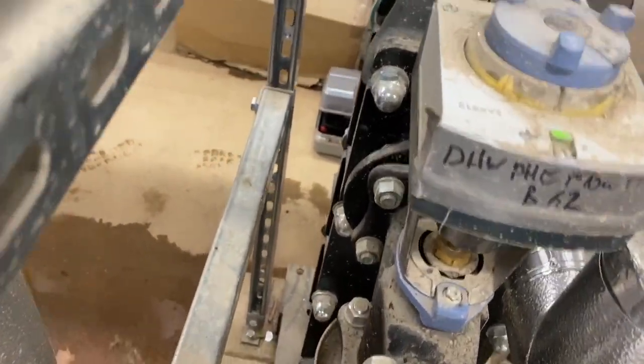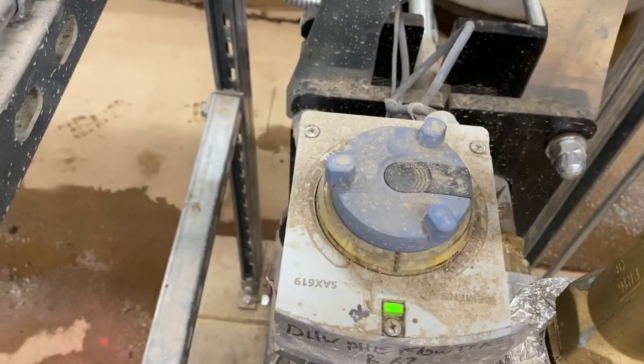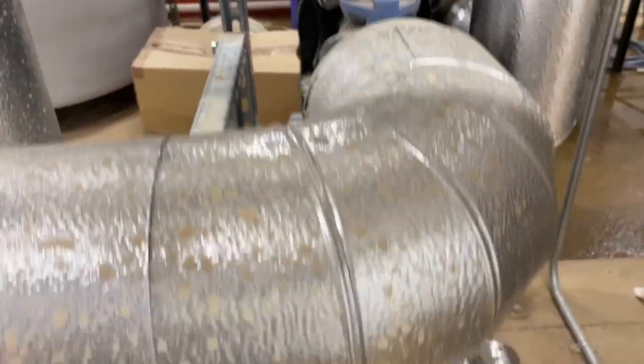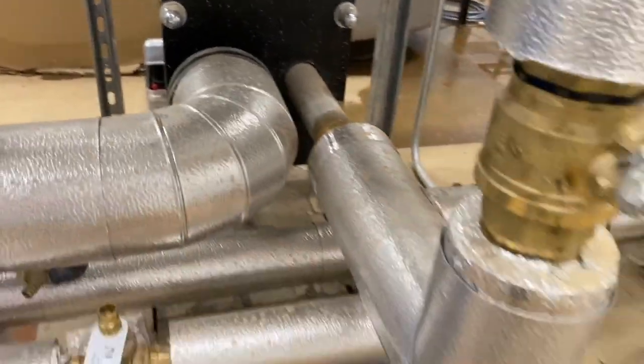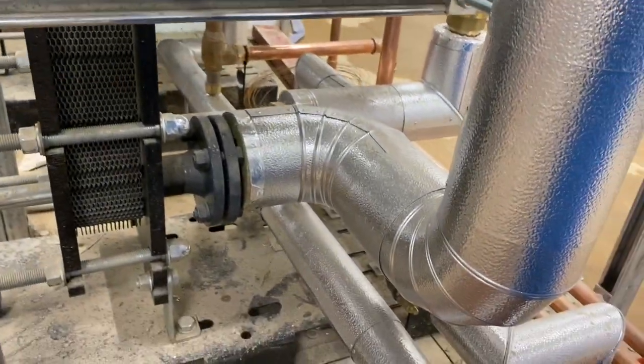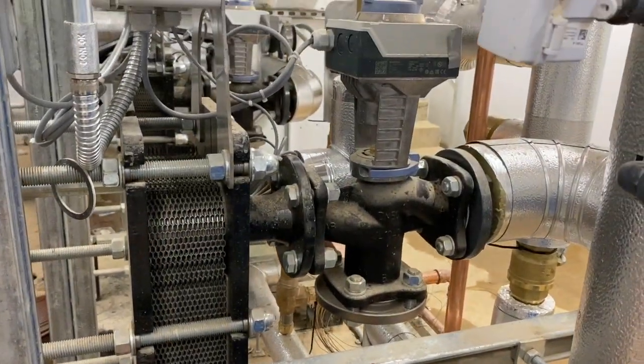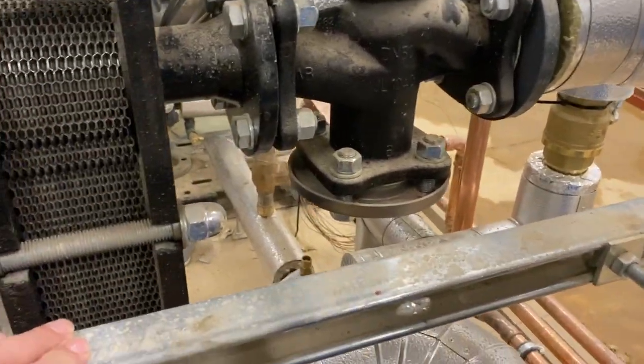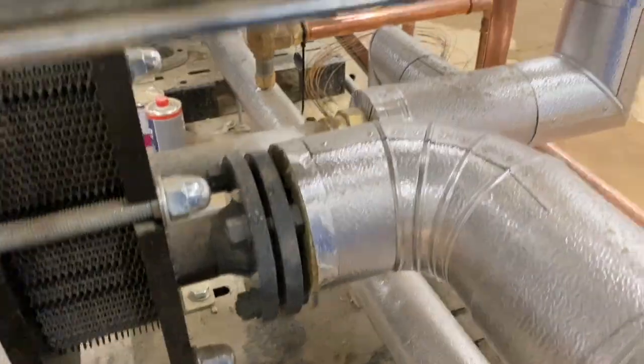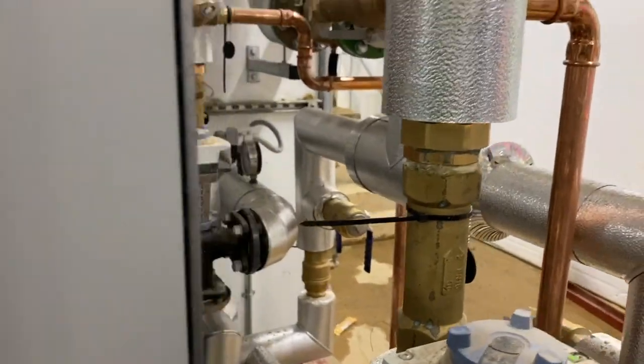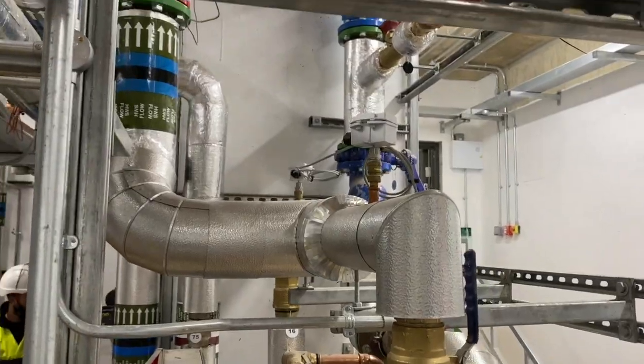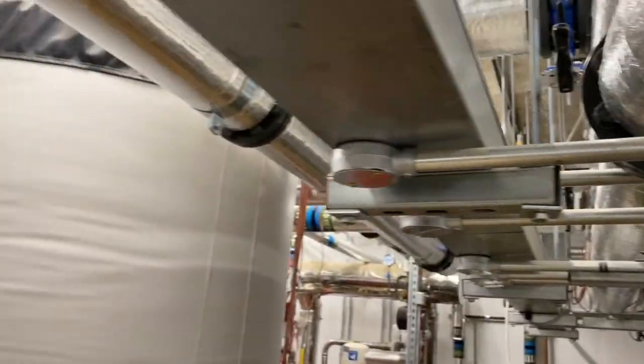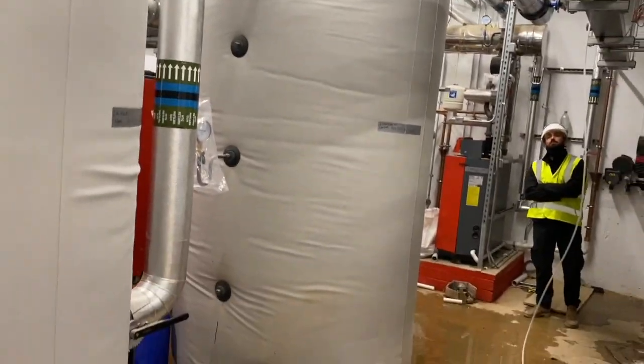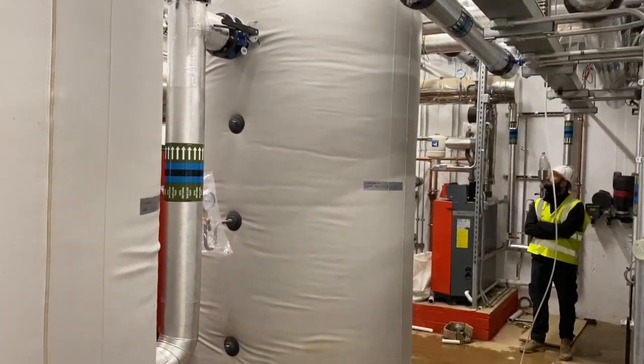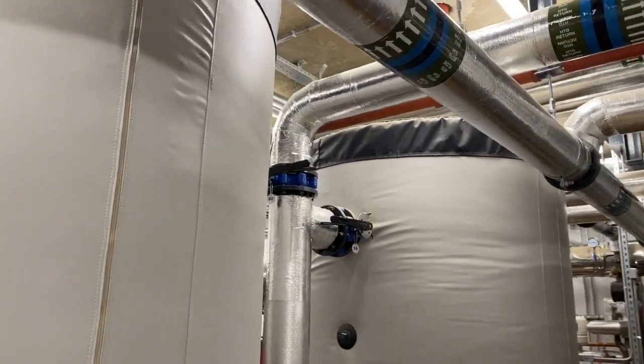You see there's a three-way valve moving around, adjusting the primary circuit from the boilers or heat source to give us the right amount of heat out of the plate. It's a primary circuit and two-port valve on this particular one. So it's just opening and closing the valve as needed relative to the demand. We'll make sure there's isolation valves. Again, that non-return wouldn't really be there. Should be further back as per just a mere standard G3 setup.